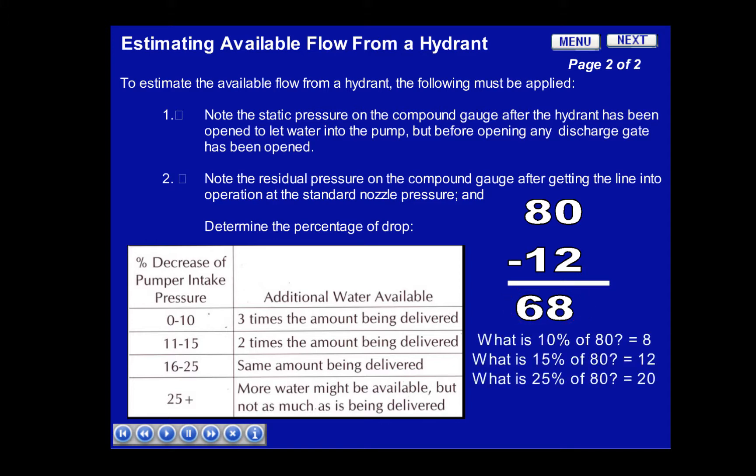The simple way to determine the percentage loss of your static pressure is to begin by asking yourself: what is 10% of 80? In this case, that equals 8. Then simply take your answer and add half of 8, which is 4, and that will tell us what 15% is. In the case of 80, 15% is 12. Then, to determine what the 25% loss is, you simply add 8 and 12 together, which equals 20. In the case of our sample of 80 PSI, we had a loss of 15%, which was 12 PSI. Based on the 15% loss, we would be able to supply two times the amount of water being delivered.